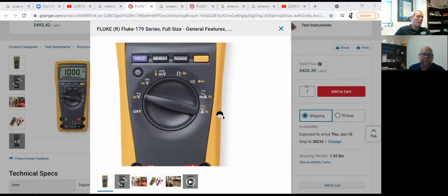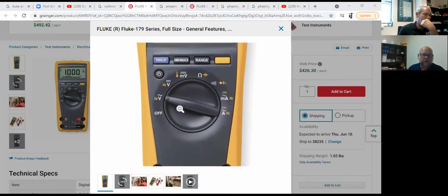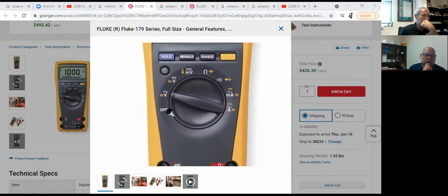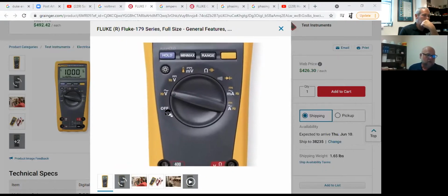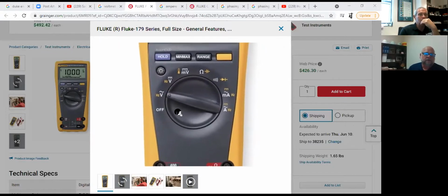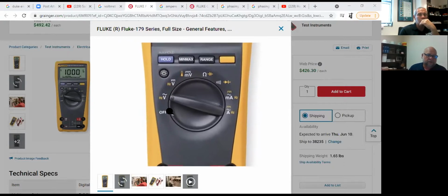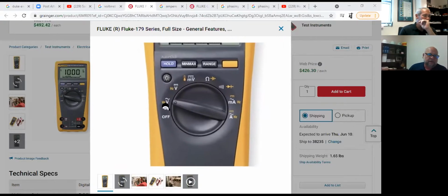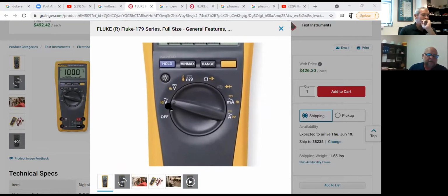Down here you can see the symbols, and I'm going to keep it enlarged so you can see it good. You got your off button, and if you leave it on, it does have a timer that will cut off after a certain amount of time to save the battery. Your first selector - this one's a multimeter - see that little squiggly line above the V? That's for AC voltage. Is that correct, Professor Shoemaker? That is - that's your sine wave, that lets you know it's AC. Correct, and that's what you want to check your voltage with, neutral or ground to phase.